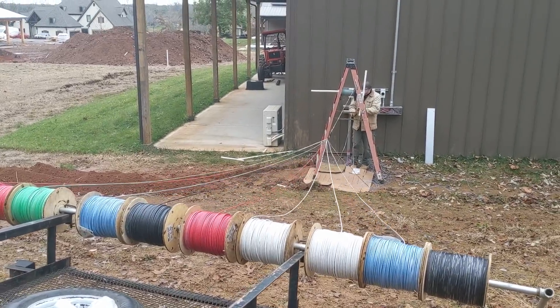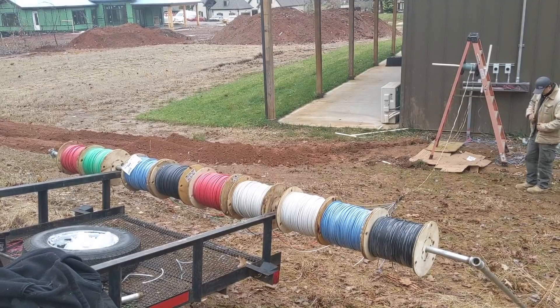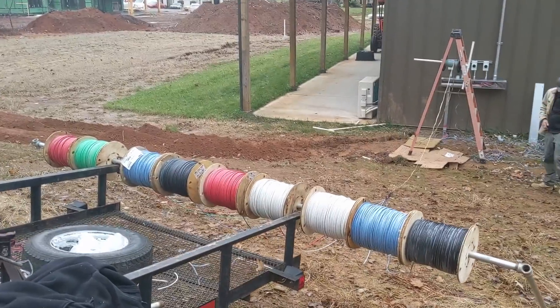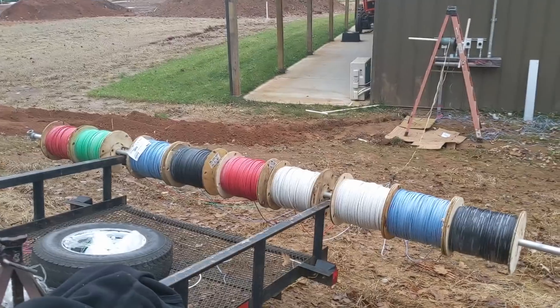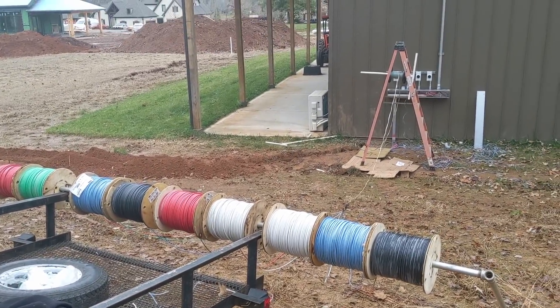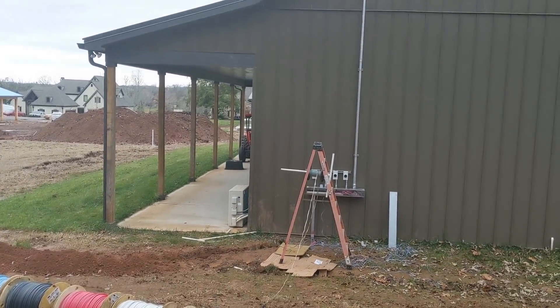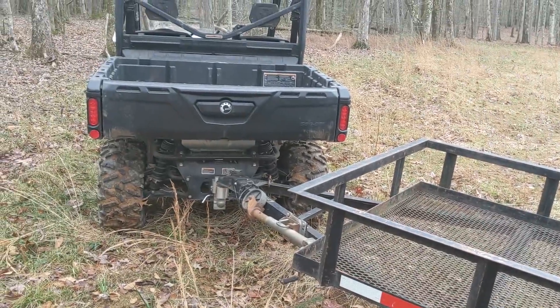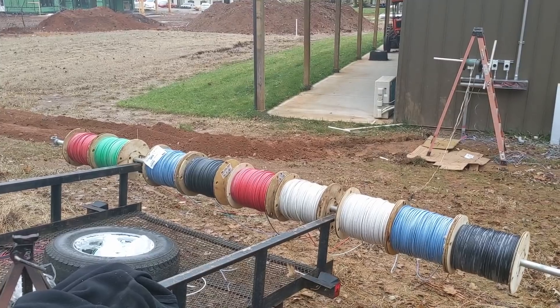Johnny's got the bull by the horns here — we're about ready to pull. We're ready to pull in our first array. We've got 9,000 feet of number eight wire for this job. Should be enough — we hope — to bring in 50 panels on this roof, and then we're gonna take this and drive it over to our other conduit setup and pull in the other 42 panels' worth of solar.